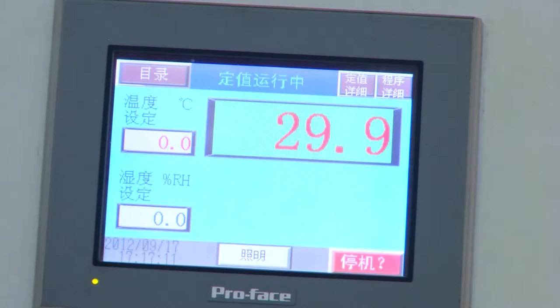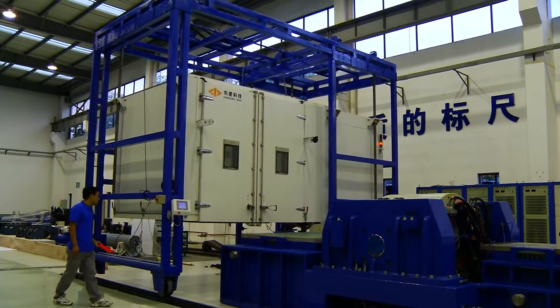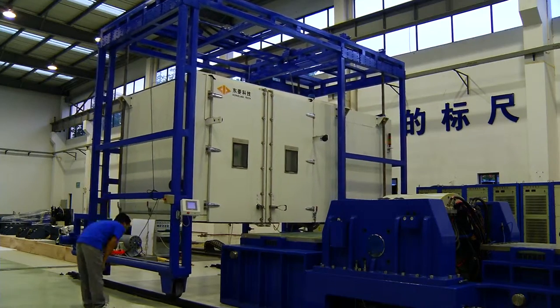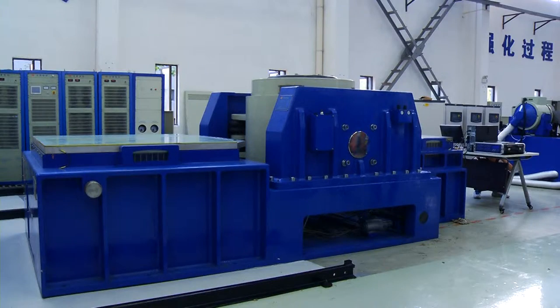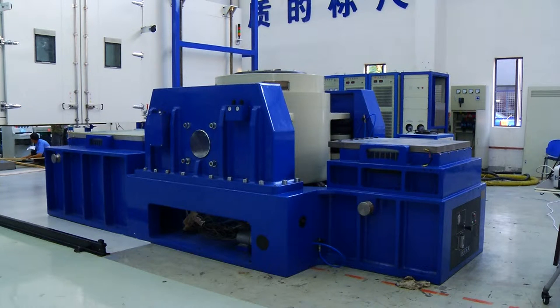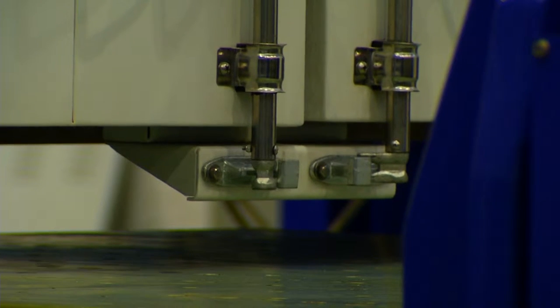The system has two slip tables with different sizes. The shaker can tilt to two sides to connect with two slip tables respectively. The large slip table is 1.5 meters by 1.5 meters and small one is 0.8 meters by 0.8 meters.